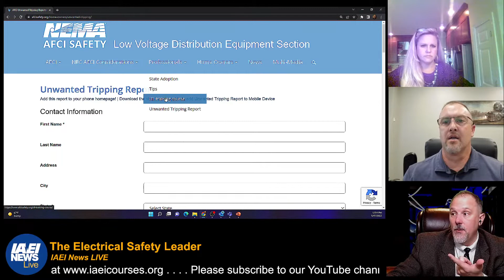We put that together because of what Donnie just said—some people don't have that skill, they say they don't like troubleshooting or aren't good at it. That educational program we worked on with UL breaks it down to help people understand some of the thresholds, like series arc detection starting at 5 amps, and parallel arc detection starting at 75 amps, meaning you might need to put some load on the circuit to get the breaker to recognize a problem.